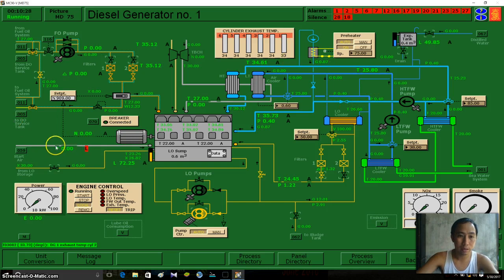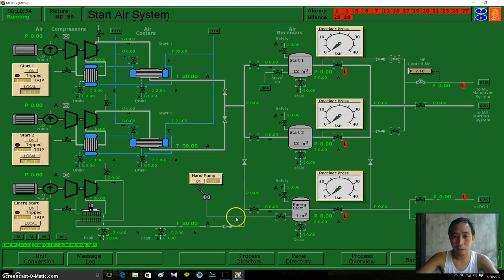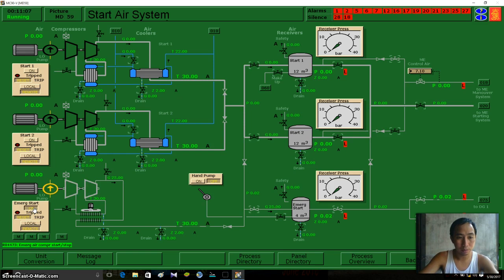The next one is the starting air. So we're going to our starting air system, that is MD 59, and we are going to fill our emergency starting air tank. So check the line from our pump, from our compressor. We have our line here. So we're going to open the valve from here and the outlet going to your diesel generator 1 and number 2. We're going to fill this one by starting our emergency air compressor.